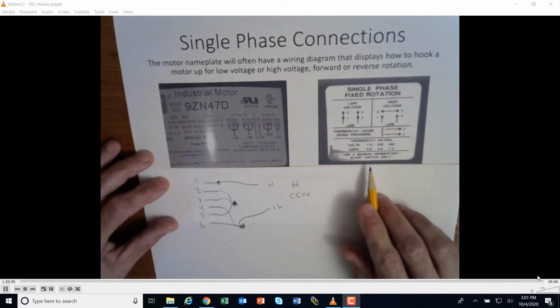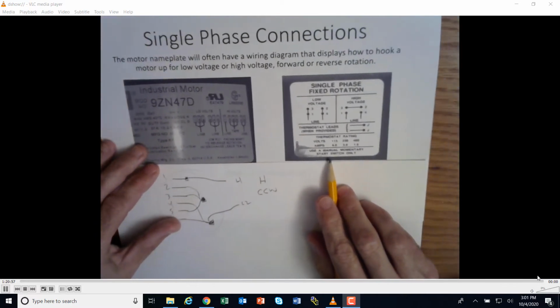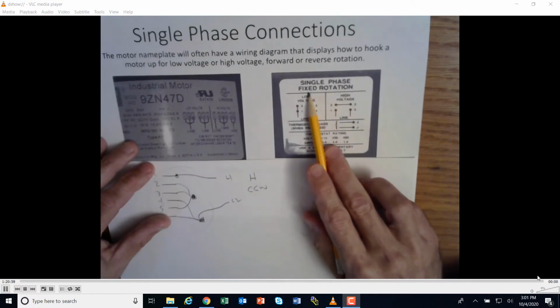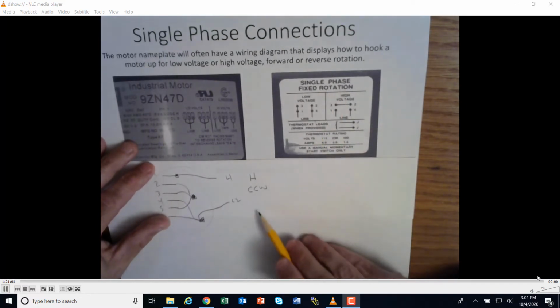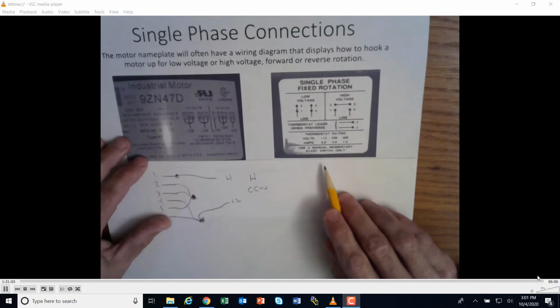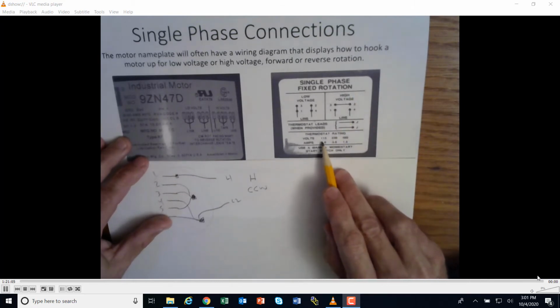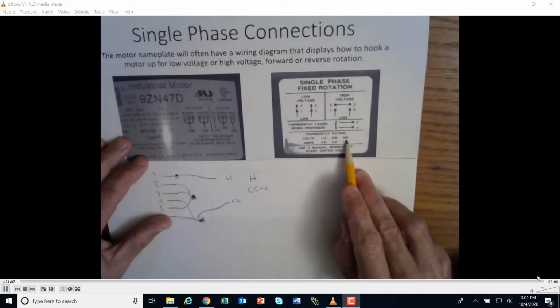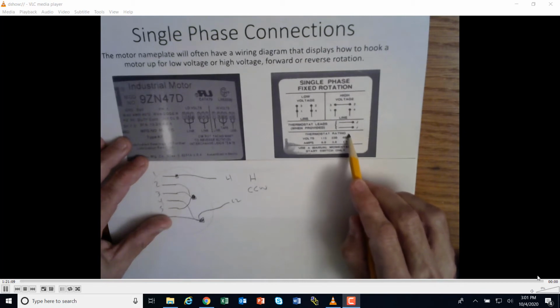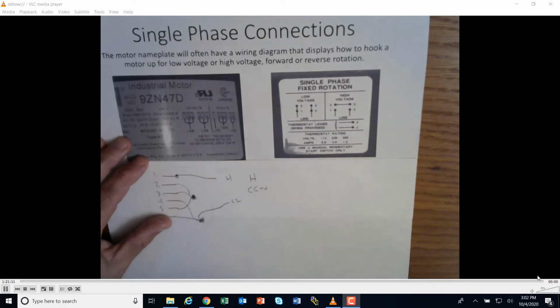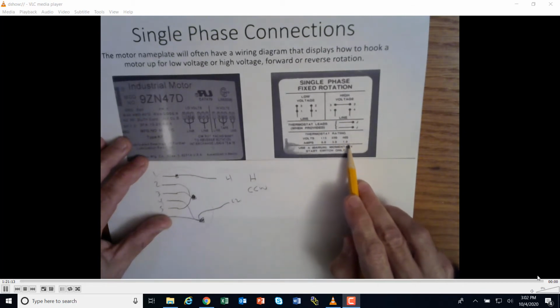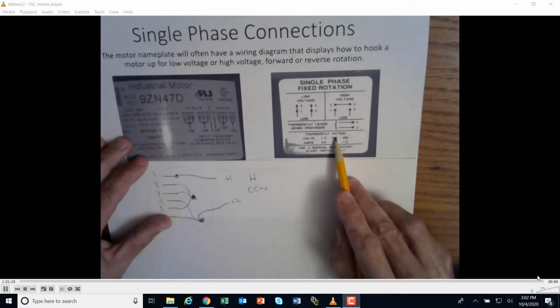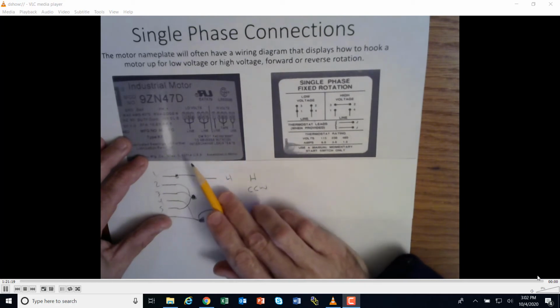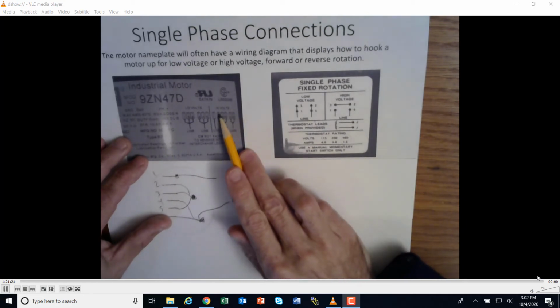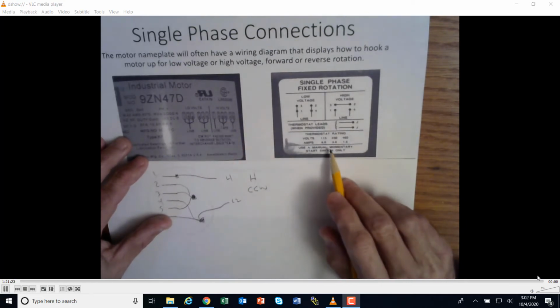On this next motor here, we're going to take a look. So this is a single-phase fixed rotation, and we're assuming that it is single phase. Yep. So it's listed here by volts: 115, 230, 460. Now 460 single phase is not really that popular. You don't see it quite as much as you would see 115 and 230. Okay, so that's why we used high voltage here. We're talking about 230 or 240, not 460.